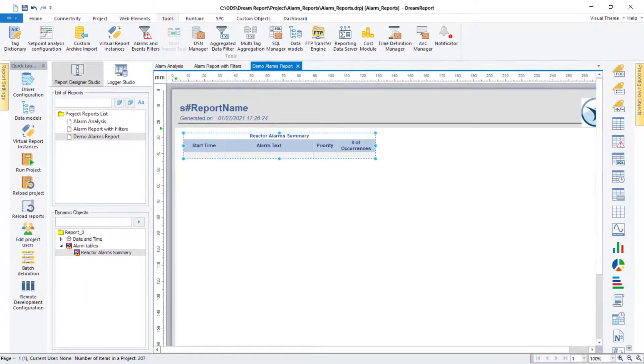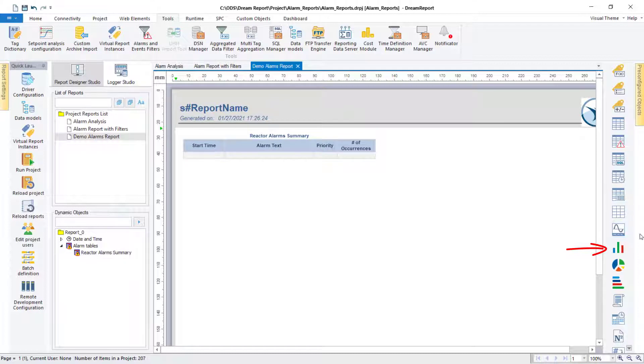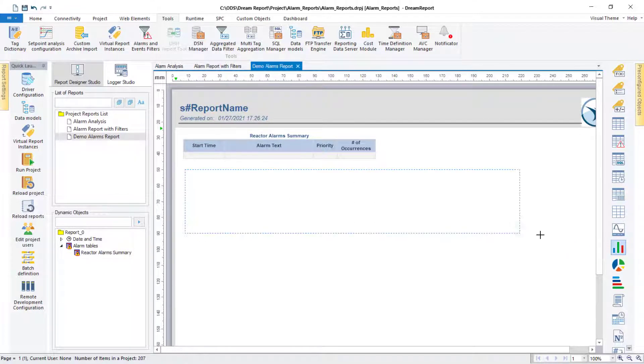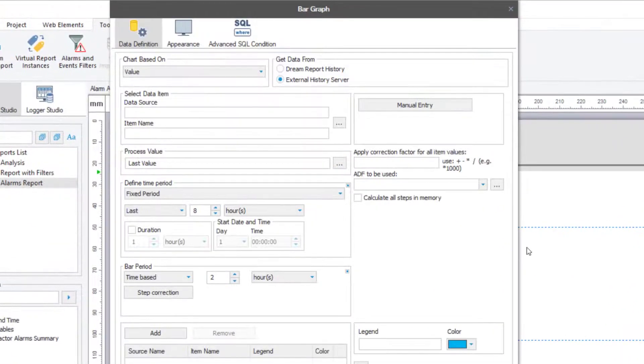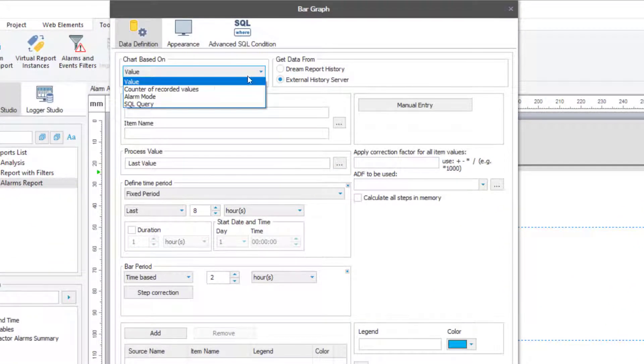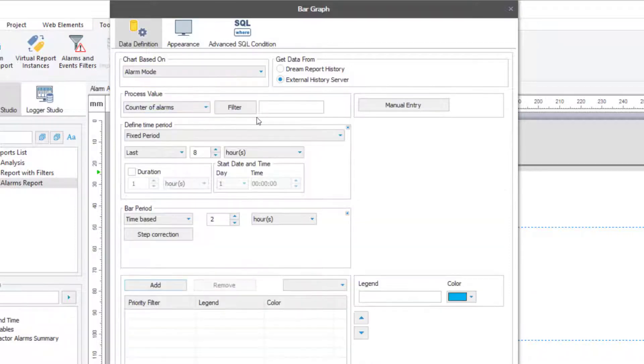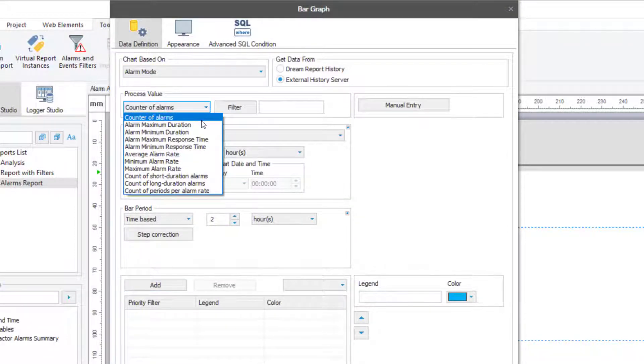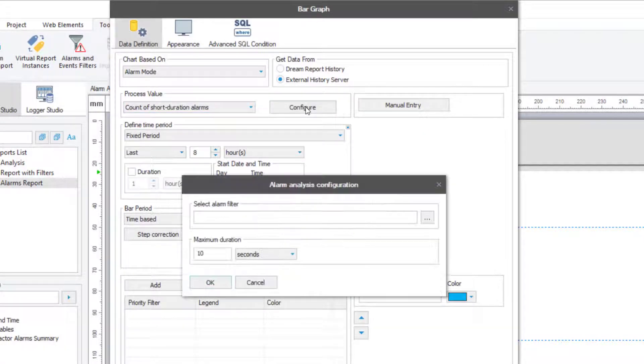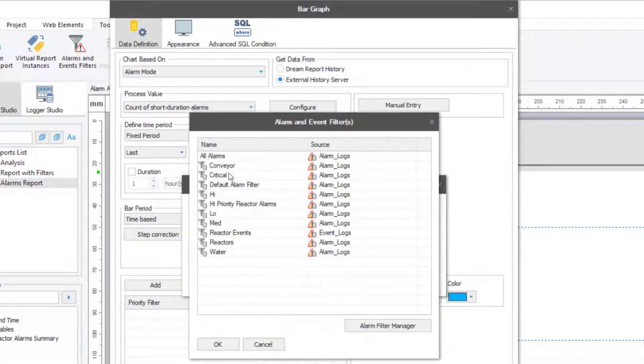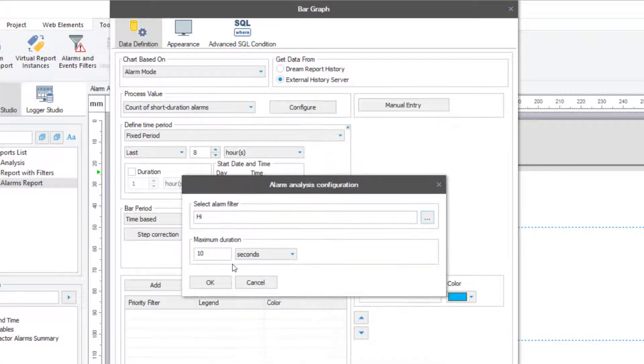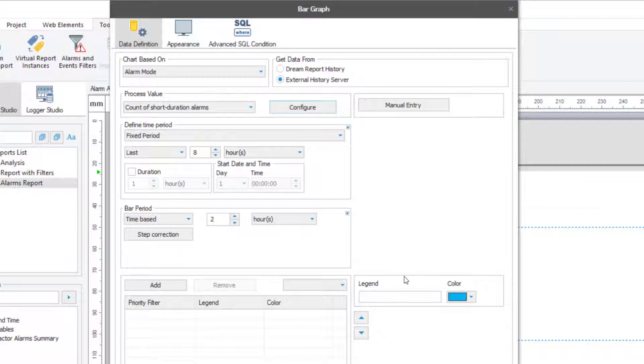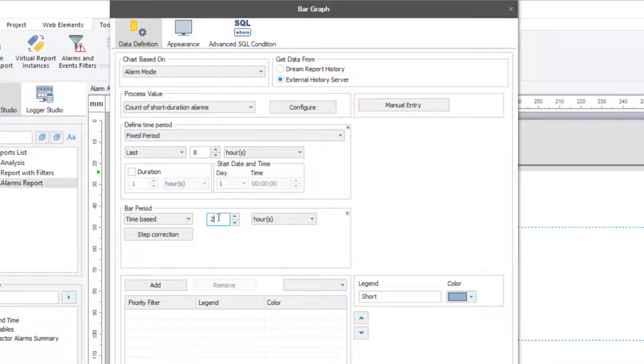The next object I'll add is a bar chart, where I want to see the split between the number of short and long duration high priority alarms by hour for a shift. I'll add a bar graph here. The chart will be based on an alarm mode. Once I select that option, we can then pick which alarm metrics we want to use. I'll first pick the count of short duration alarms, and then select the predefined high priority filter. I then need to configure this to look for alarms less than 10 seconds in duration. The overall time period for the chart will be the last shift, and the bar periods will be one hour. Let me name this bar, and then add it.